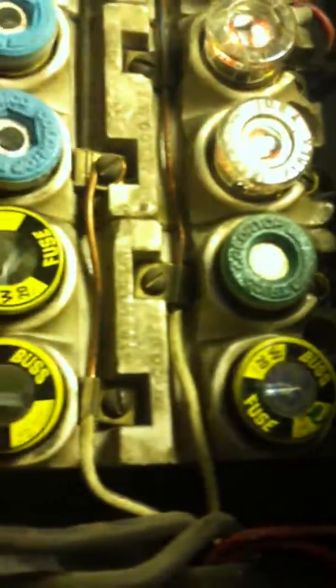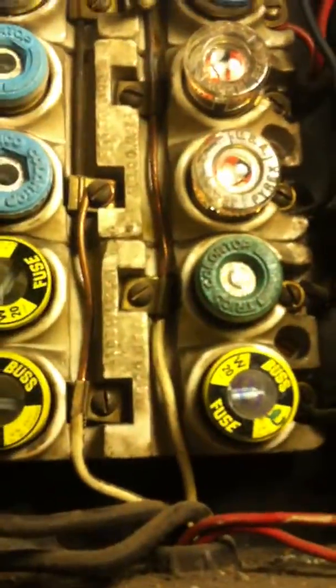Why? This is where the fires start, because a lot of this wire in here is not even 14 gauge — it's a little less than 14 gauge, probably closer to 15 gauge, but classed as 14. 14-gauge wire is rated for a maximum of 15 amps per national code.